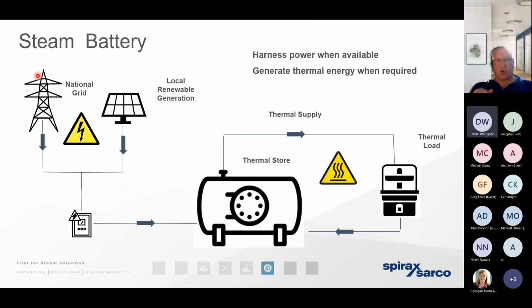Now, taking that one step further, Spirax Sarco has also got a product that's at a very, very advanced stage of commercialization. It's what we call the steam battery. And the steam battery is a kind of thermal store, and thermal stores are very common in other industrial applications. But the way the steam battery works is, if we take a pressurized vessel of water and elevate the pressure and the temperature, we can go back to the fundamentals on the steam tables that we looked at. Let's say we elevate the pressure of the thermal store to 30 bar gauge. That means the water's sat there as a single phase liquid at 225 degrees.